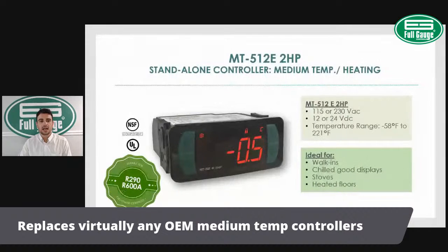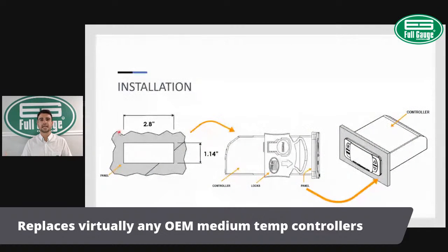One thing that I would like to highlight in here that this 512 is ideal for, it's certified for R290 and R600 applications. So those flammable refrigerant applications are also a good application for the 512. So this becomes a really good replacement for OEM controls out there. Installation. Controller has the same cutout, the same dimension as the other controls. So it keeps the same footprint, the same cutout as the existing OEM controls.